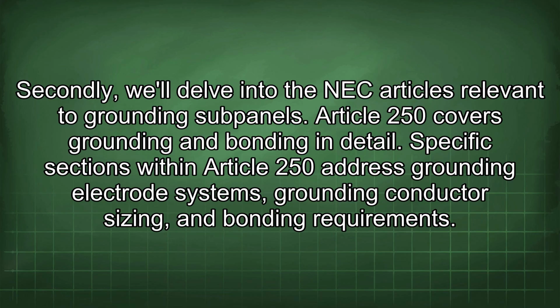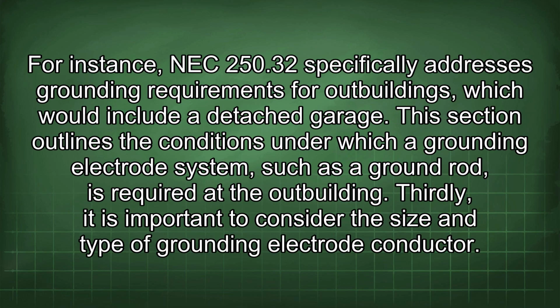Secondly, we'll delve into the NEC articles relevant to grounding subpanels. Article 250 covers grounding and bonding in detail. Specific sections within Article 250 address grounding electrode systems, grounding conductor sizing, and bonding requirements. For instance, NEC 250.32 specifically addresses grounding requirements for outbuildings, which would include a detached garage. This section outlines the conditions under which a grounding electrode system, such as a ground rod, is required at the outbuilding.